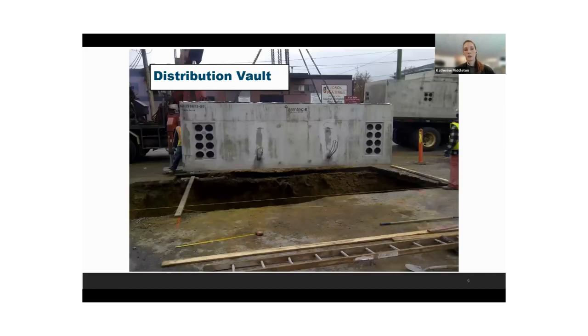Here's a good picture of a distribution vault. As part of our underground system, we have underground vaults, essentially big concrete boxes that we need to install in the ground. We need these vaults typically for cable being pulled through the ducts. There's a limitation on the distance we can actually pull an underground cable before we have to stop and begin a new pull. If we pull for too long of a distance, the forces on that cable will damage or break it. So that's a consideration we have to account for.